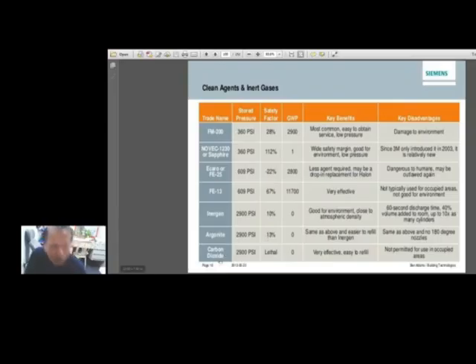Carbon dioxide, this is 2,900 PSI. It is lethal because it totally displaces oxygen. Very effective, easy to refill. Not permitted to use in occupied areas. So, like I said, if you have occupied areas, if you have people working inside the rooms, then you do not like CO2. Okay?